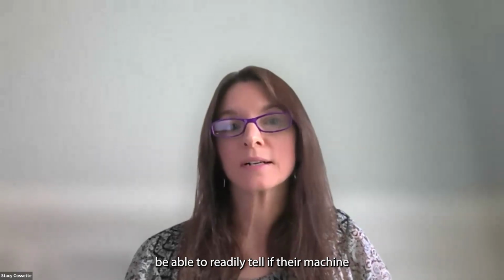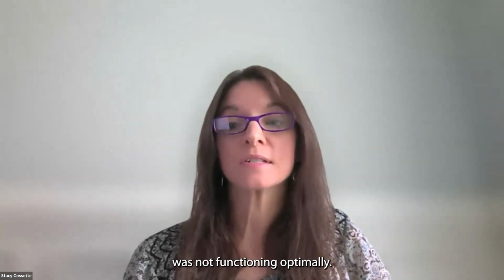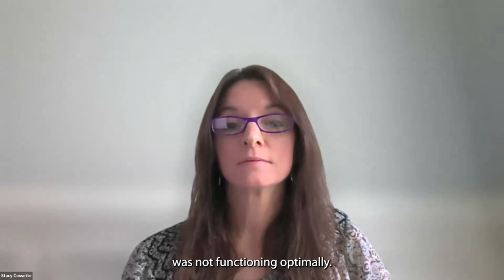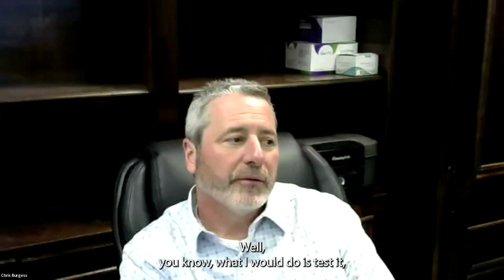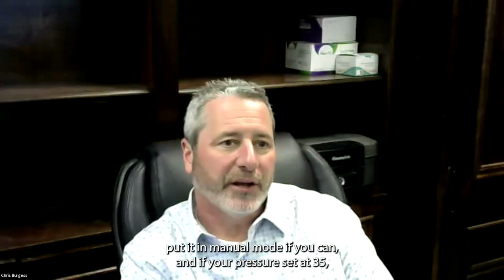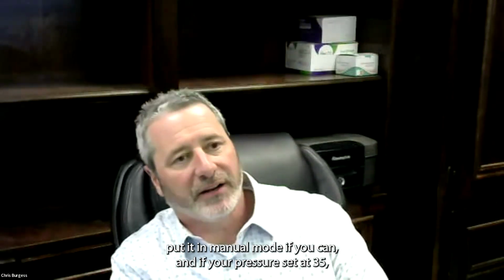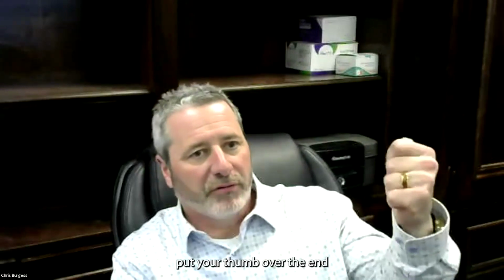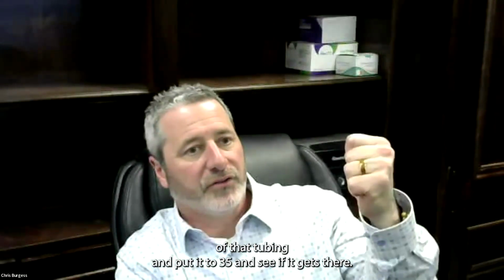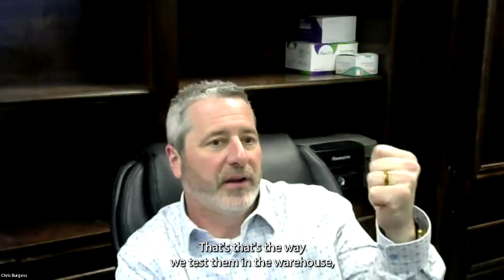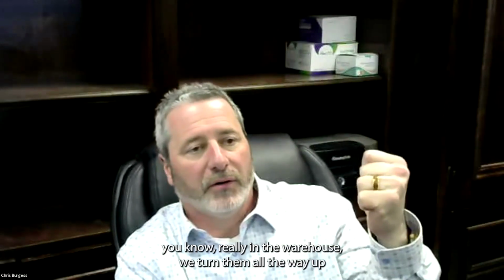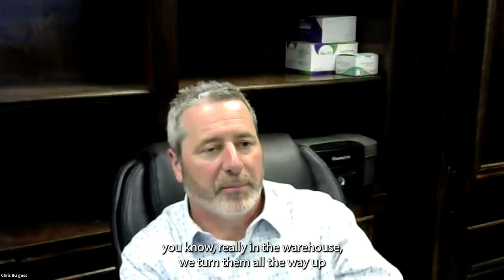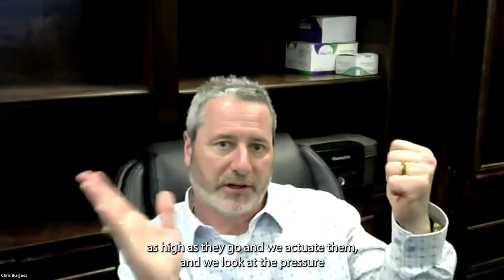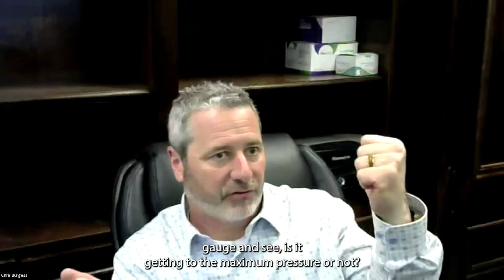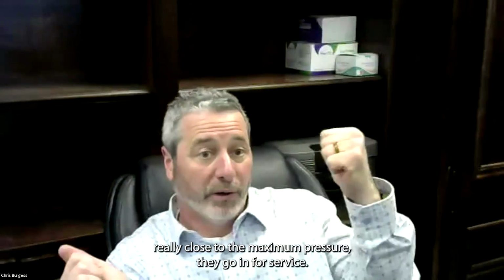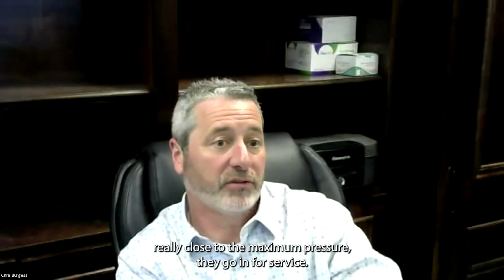Would the patient be able to readily tell if their machine was not functioning optimally? Well, what I would do is test it, put it in manual mode if you can. If your pressure's set at 35, put your thumb over the end of that tubing and put it at 35 and see if it gets there. That's the way we test them in the warehouse. We turn them all the way up as high as they go, and we actuate them, and we look at the pressure gauge and see, is it getting to the maximum pressure or not? If it doesn't get at least really close to the maximum pressure, they go in for service.